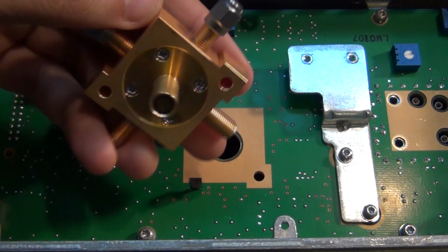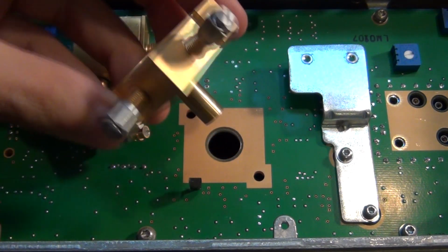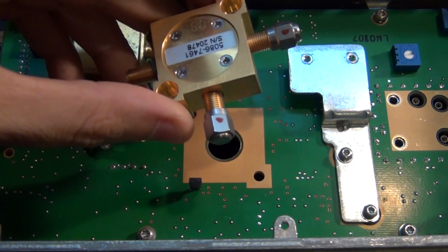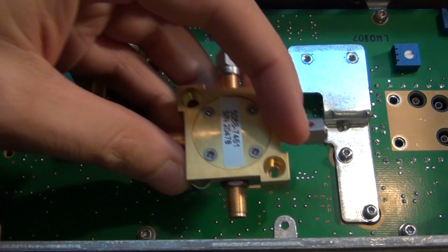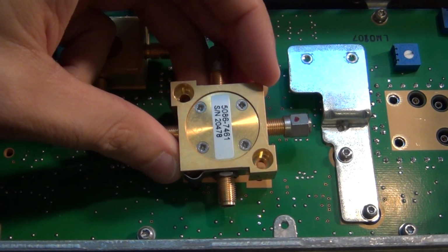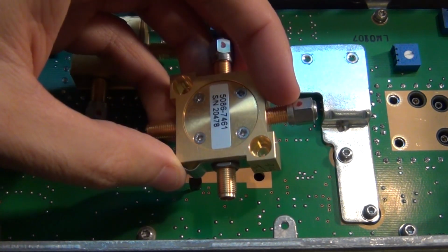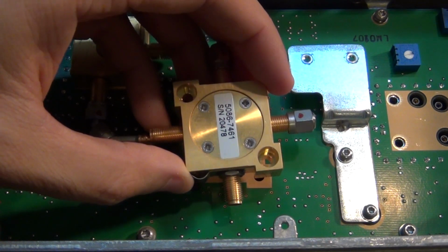And here's the pulse shaping unit taken out by itself, again a completely custom module. And one thing I forgot to mention is that this component that you see here is just a junction diode used to measure the temperature of this. This is a temperature detector, and they have it captured in this little clip here, which presses against the body, monitoring the temperature.